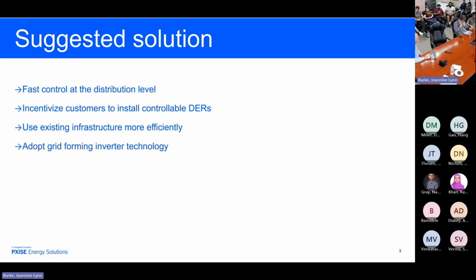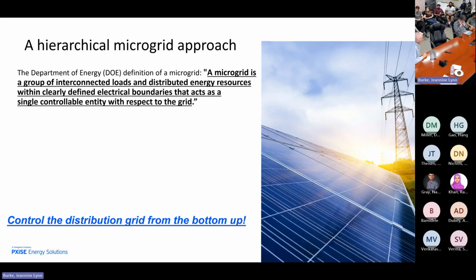And finally, we have to get over this grid forming inverter problem. The industry is totally rejecting the idea of grid forming inverters in microgrids. They insist on everybody being grid following, and in particular, the diesel generator being the lead grid forming device in a microgrid. We don't want the diesel generator to run at all, unless there's an extended outage, then the diesel generator runs.